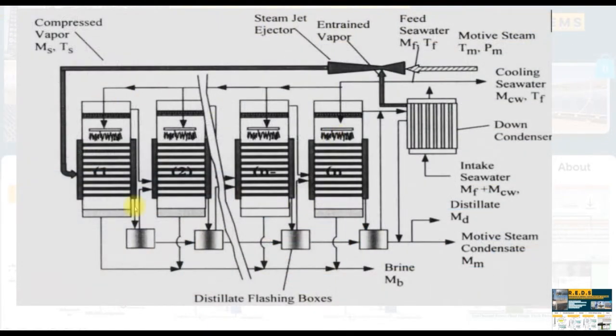This is the process of MED thermal vapor compression. This is the end condenser and this is the entrained vapor from the end condenser. This is the motive steam coming from the solar field. This is the compressed vapor going to power on the first effect thermally, and the process will continue simultaneously. This is the cooling feed water — we have intake of total feed water which feeds the MED and the cooling water for the condenser unit.